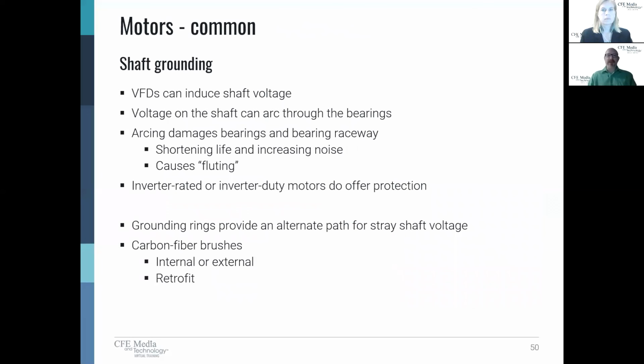Now, we prevent bearing damage in motors whenever we use a VFD through what's called shaft grounding. It's important to note that the concept of a VFD is it has a high frequency switching, and that high frequency switching can generate a lot of higher voltages. It can also cause arcing. So if we don't have individual shaft grounding, which is separate from the motor itself, if we don't add that, then we can actually arc across the bearings. And if you have bearings that fail quickly or become noisy fairly quickly, that's probably a result of the arcing that's occurring. Now, luckily, it's pretty easy to either specify shaft grounding or even add it after the fact.